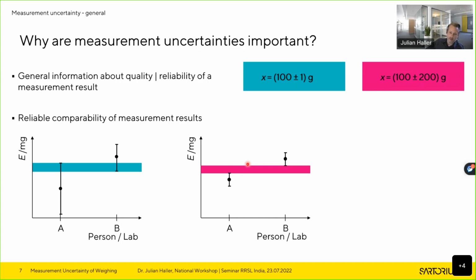And this of course looks much different if you take into account the measurement uncertainties. Now, in the left example, you will see there is an interval or a region where the two results, including the measurement uncertainties, overlap, which means if the true value is here, actually both persons or labs have respectively measured the correct result, which means these two measurements are compliant with each other. But in the other example, you see there's no overlap, which means they contradict each other. So in this example, you as the boss or lab manager would have to undertake respective action to either find out why person or lab A or B measures not correctly, or if they have to state bigger uncertainties.